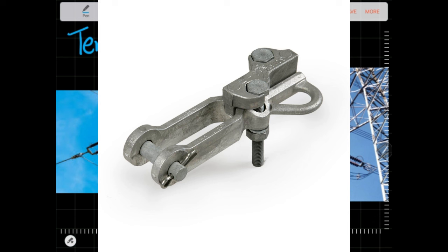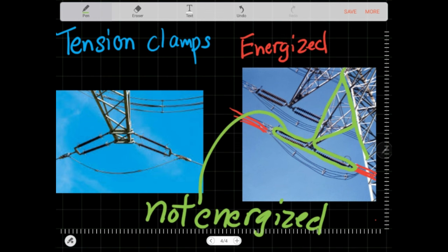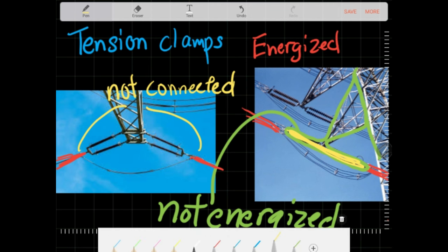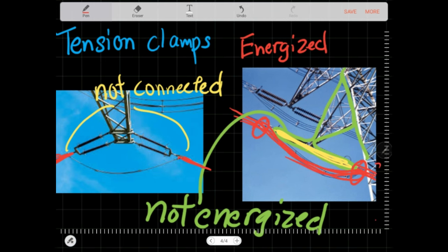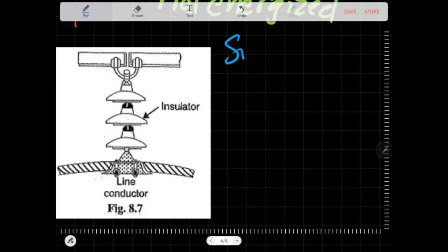Tension clamps. They connect the tension transmission lines before the insulators. The lines are energized. The tower isn't energized. The insulators prevent the energized equipment from spreading. Essentially this line here and that line here are not electrically connected. That is where the clamps and the jumper cables come in to make the connection. It is important that the clamps are connected well. This is because joints such as clamps are prone to hotspots if the contact is loose or not well done. Hotspots may cause higher resistance and reduce power flow. That is not good.